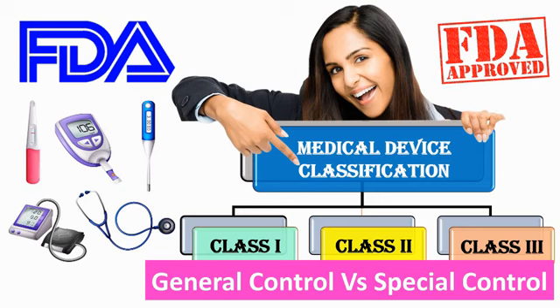Today we are going to look at medical device classification. Classification is arguably one of the most important steps in the FDA medical device approval process, and understanding how the US FDA classifies devices is critical for identifying the proper regulatory pathway, that is either the 510K or the PMA.